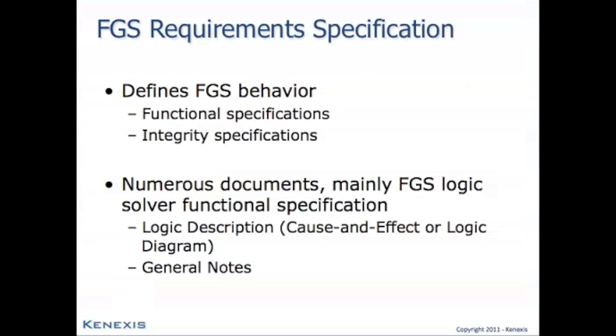After all of the loops have been verified to achieve their safety availability target, the final design needs to be documented in an FGS requirement specification, sometimes called an FGS safety requirement specification. The FGS requirement specification defines how the fire and gas detection and suppression system will perform, and it is essentially a design specification that is the basis for the supply and the engineering of the FGS equipment.